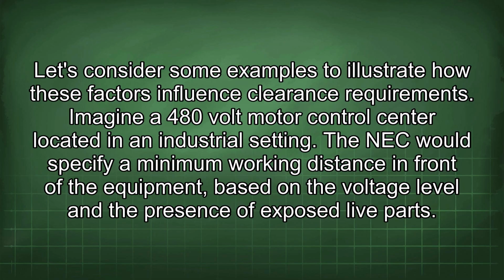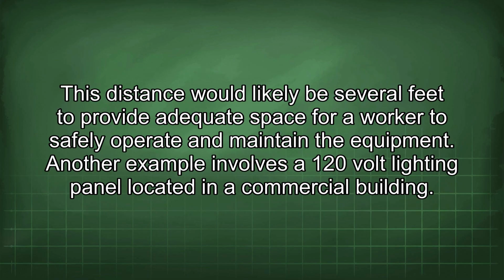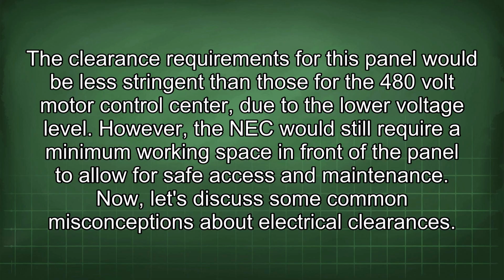Let's consider some examples to illustrate how these factors influence clearance requirements. Imagine a 480-volt motor control center located in an industrial setting. The NEC would specify a minimum working distance in front of the equipment based on the voltage level and the presence of exposed live parts. This distance would likely be several feet to provide adequate space for a worker to safely operate and maintain the equipment. Another example involves a 120-volt lighting panel located in a commercial building. The clearance requirements for this panel would be less stringent than those for the 480-volt motor control center due to the low voltage level. However, the NEC would still require a minimum working space in front of the panel to allow for safe access and maintenance.